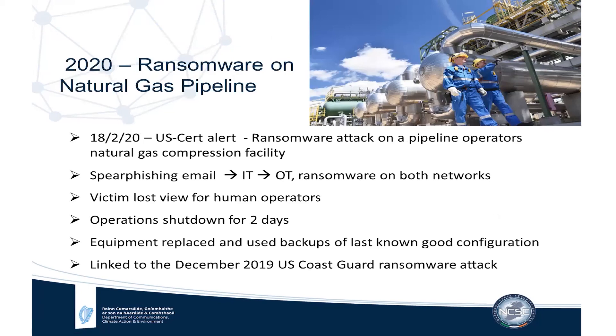A ransomware attack on a natural gas compression facility was reported by US-CERT on 18 February 2020. The attack entered via a spear-phishing email onto the IT network and spread to the OT network. Ransomware on both networks caused operators to lose visibility of the process. The plant was still operating safely, but since operators couldn't see what was happening, they had to shut down for safety reasons. Equipment had to be replaced and last-known-good configuration backups were used. The incident is also linked to an attack on the US Coast Guard the previous December.